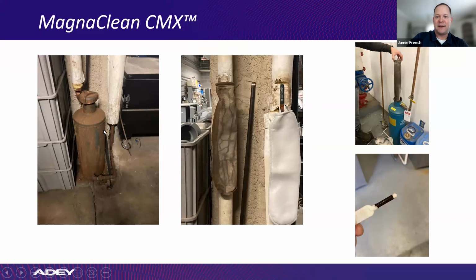These guys are going to put a Maxi in. But here's where I was talking about with that value engineering. If they don't want to go full on replacing their chemical pot feeder, or if you're specifying one and still want magnetic protection, that's where the Nano would fit in. You can pipe it right in line with this thing. So you've got your magnetic filtration, your dose pot here, and your non-magnetic filtration. All kinds of options.